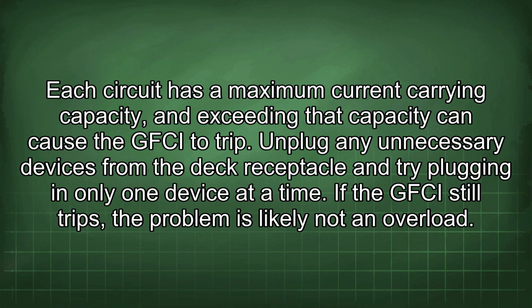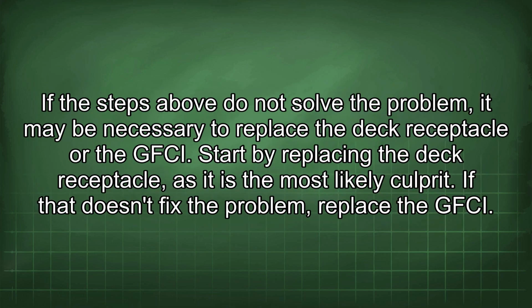Each circuit has a maximum current carrying capacity, and exceeding that capacity can cause the GFCI to trip. Unplug any unnecessary devices from the deck receptacle and try plugging in only one device at a time. If the GFCI still trips, the problem is likely not an overload. If the steps above do not solve the problem, it may be necessary to replace the deck receptacle or the GFCI. Start by replacing the deck receptacle, as it is the most likely culprit. If that doesn't fix the problem, replace the GFCI.